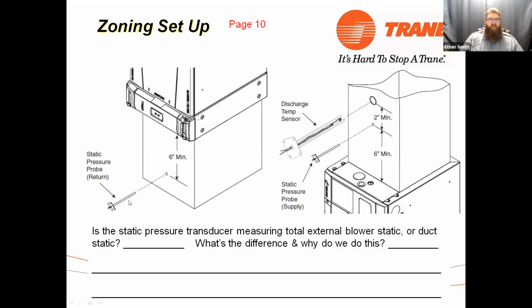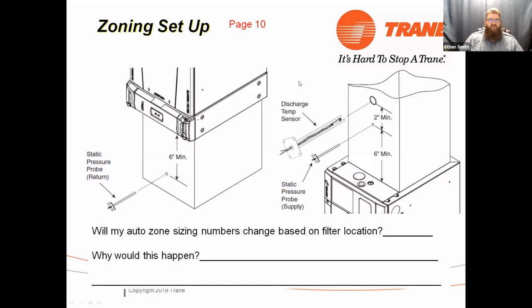Okay. On our return side, we want to be a minimum of 6 inches away from our filtration. And so we are measuring the total external static, or duct static, on this application, and the zoning controls will actually use that to calculate our zone sizes based on our duct static. So that's why we use duct static rather than blower static.